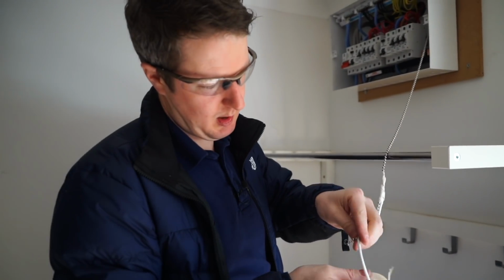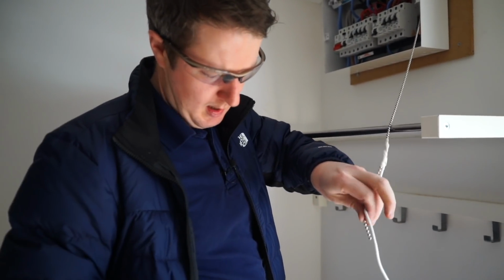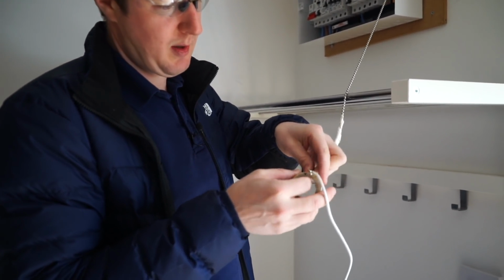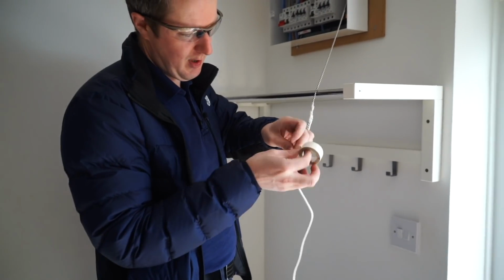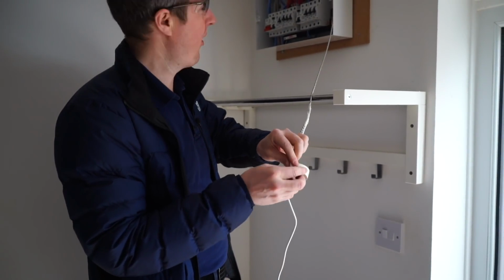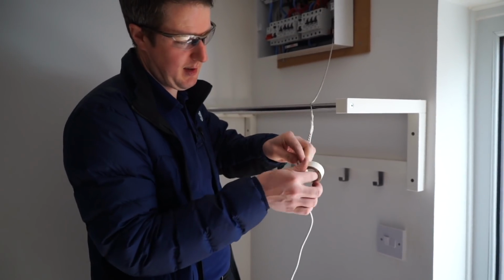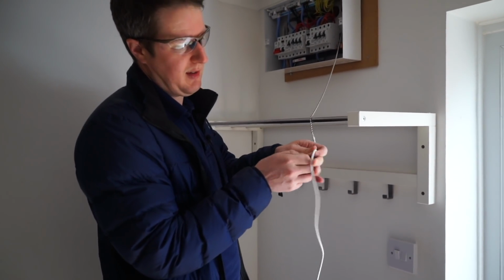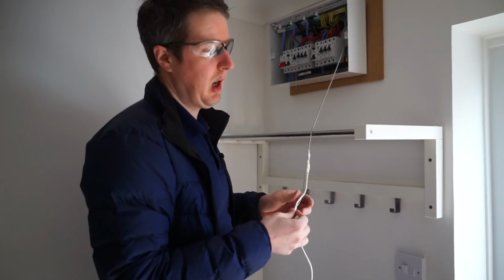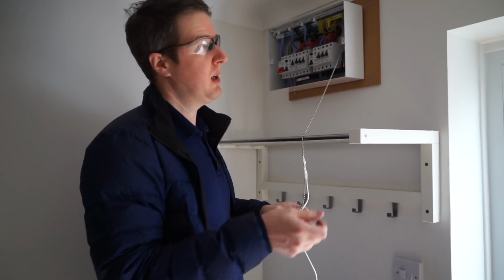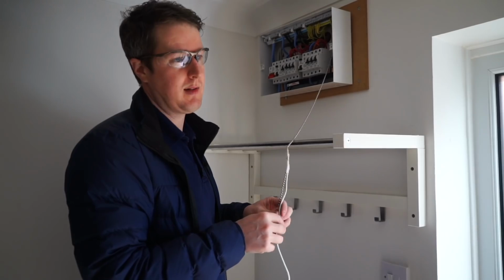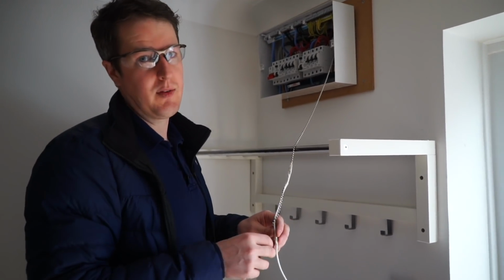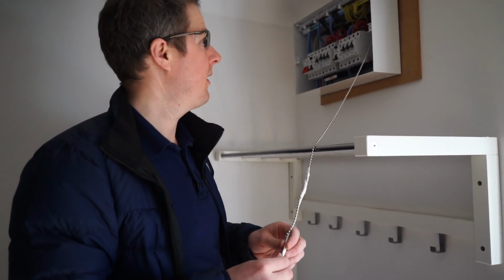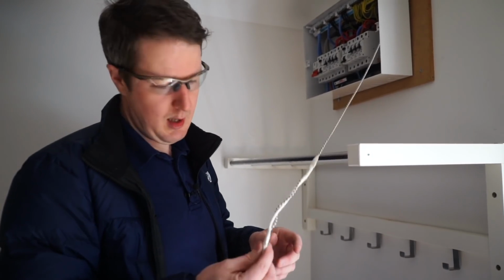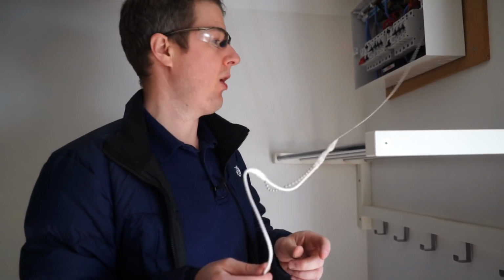So what I'm doing is using this cable from the transformer supplied with the doorbell. It's rated at 300 volts, so it's absolutely fine to be in the consumer unit. That's obviously something you need to consider. For example, if you're using single insulated cable, like normal bell wire, you shouldn't really use that in the consumer unit - you'd have to sleeve it to make it rated at the right voltage. But this one says 300 volts on the cable, so that's fine.